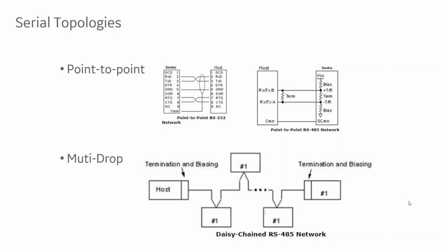So all we need to do is grab the data in a certain address, and then we'd have to go and look up what that address is. So some of the newer protocols like 61850, it's not an address, it's actually a description. So it's a description of that address. So once you say, hey, I want A-phase current, and you go to Relay A, it will know exactly what A-phase current is and give it to you. You don't have to say, hey, give me address 4001. You just tell it exactly what you need, and it will know what to give to you.